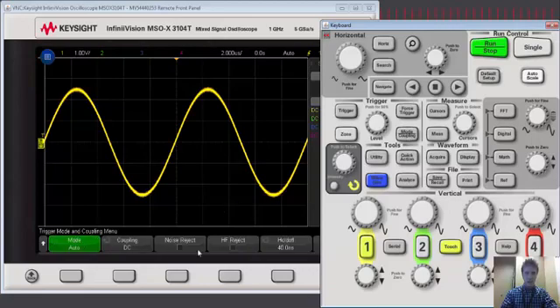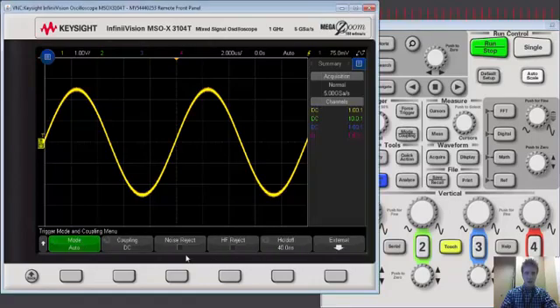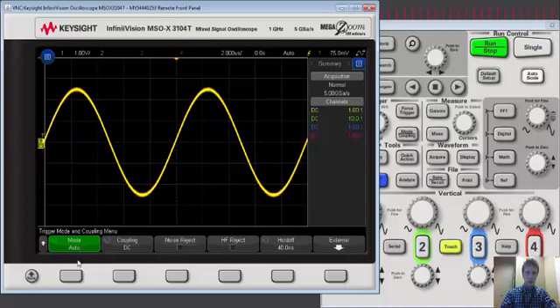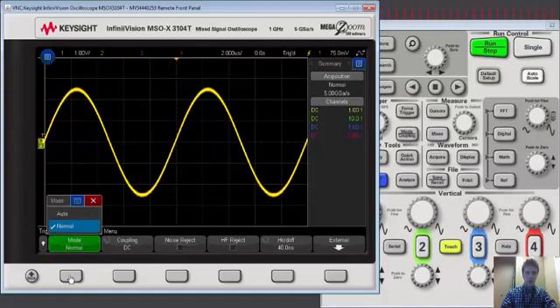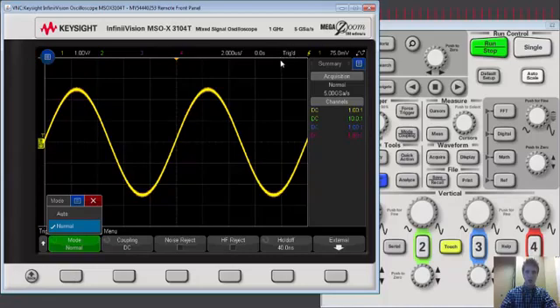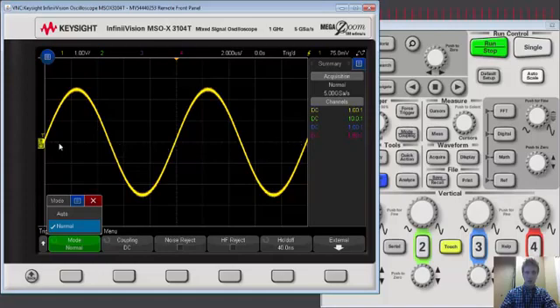This will update the soft keys at the bottom and we simply select the first soft key mode auto to change the mode to normal. And you'll see it now says triggered in the top right which signifies we're triggering on an actual event which is a standard edge trigger hovering around 50%.